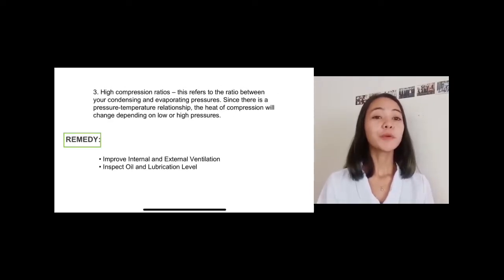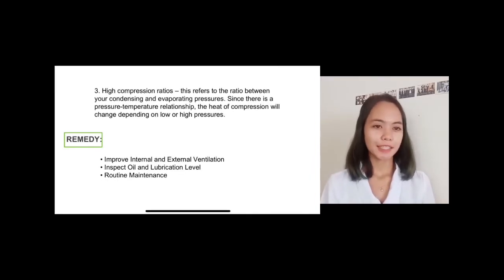Second is to inspect oil and lubrication levels. Lubrication acts as a coolant, so monitor the oil and lubricant levels in your compressor often. Additionally, if the oil is thin or appears watery, the heat level could already be too high. And then lastly, routine maintenance. The simplest action to take to prevent overheating is to have routine maintenance performed on your compressor.